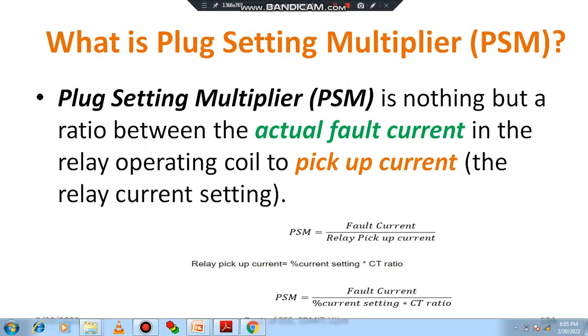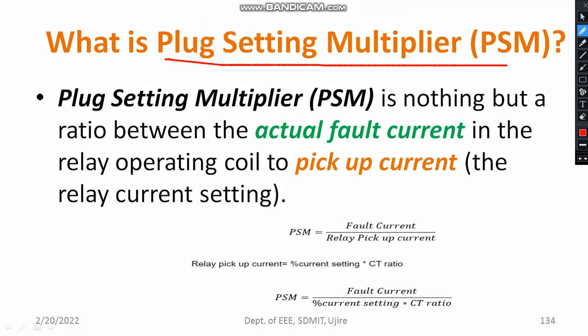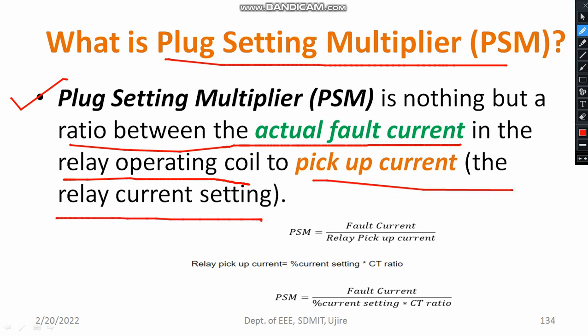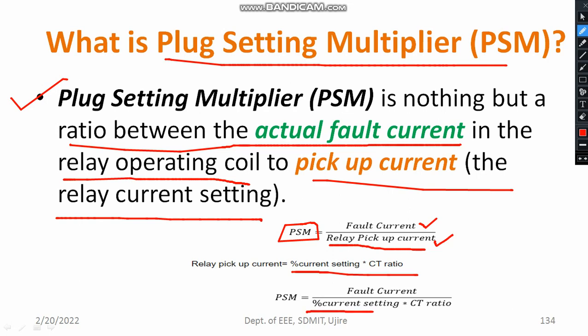Another important setting is called plug setting multiplier, short form PSM. The plug setting multiplier is nothing but the ratio between the actual fault current in the relay operating coil to the pickup current of the relay. If you take the ratio of fault current to relay pickup current, you get PSM. Relay pickup current is nothing but percentage current setting multiplied by CT ratio. Therefore, PSM can be written as: fault current divided by (percentage current setting × CT ratio). This formula is required for solving numerical examples.